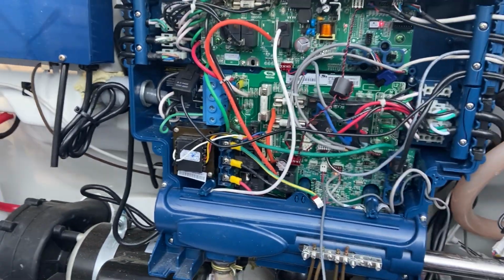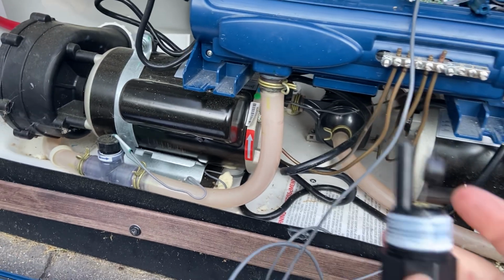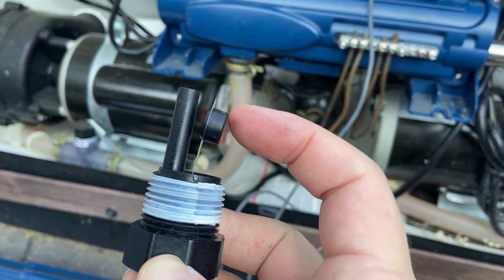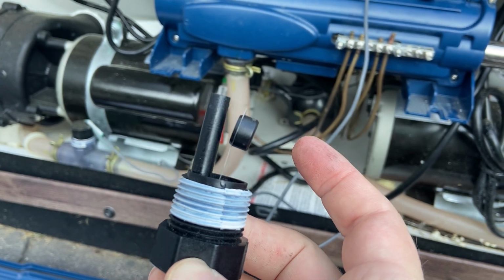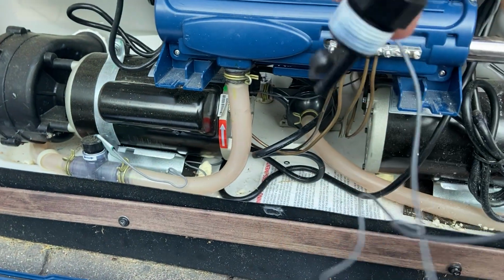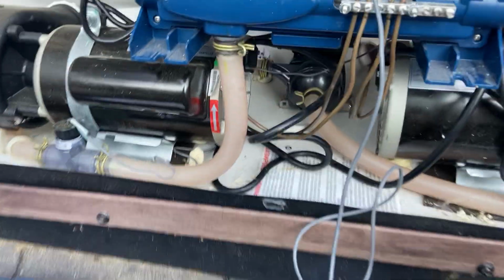So right now I'm gonna take a look. We should have a flow error. Why? Because the flow switch is in the open position. So this is open. So imagine if this was plugged in right now into the sensor T right there, and we had water flowing through it, and that switch was not closed, it would not be reading flow, even though that circulation pump is on.